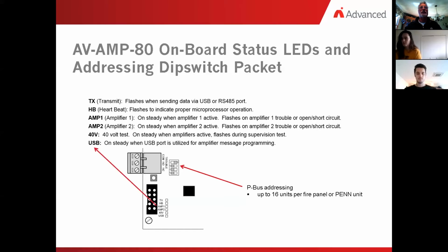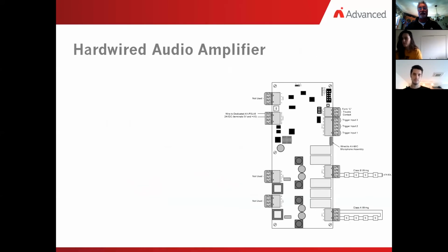So we can put these amplifiers in the VB unit out in the field. And so the dip switches are valued at 1, 2, 4, and 8. If you added up those numbers, you would see that equals 15. You wouldn't normally have an address of 0 in, say, a pull station or a smoke detector, but in fire alarm cards, a motherboard talking to its daughter cards, we use the address 0. So we have 0 plus 15, and that gives us our 16 cards.